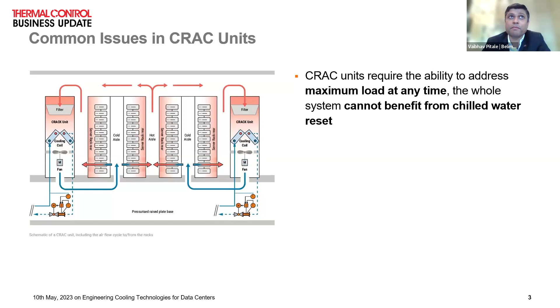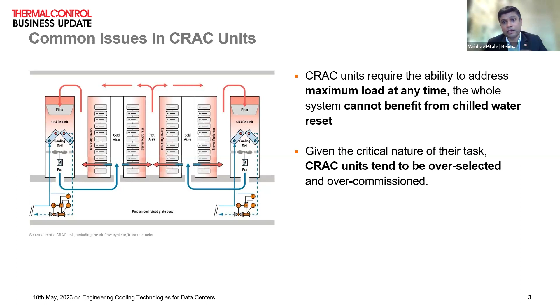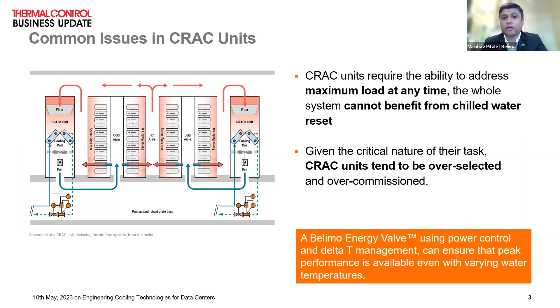When you have precise control, continuous monitoring, data transparency, and continuous load management, you also want the system to be reliable and scalable. Belimo has an energy valve, a pressure independent valve combining a balancing valve, a control valve, and a flow sensor, with continuous delta T management at the CRAC unit or AHU level rather than at the BMS level, which helps improve system efficiency and maintain temperature even at peak conditions. It's an all-in-one solution.